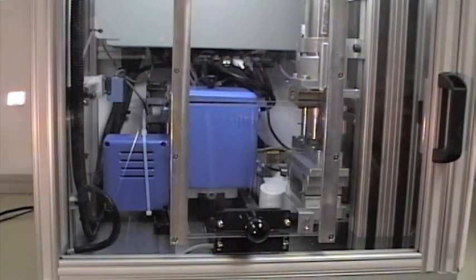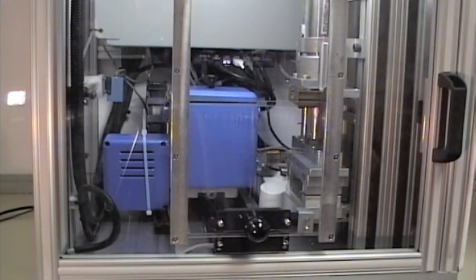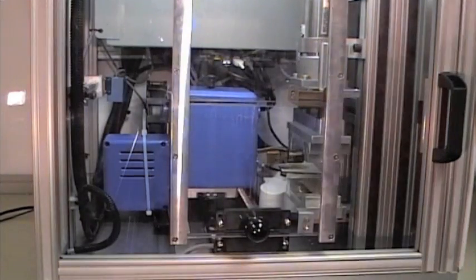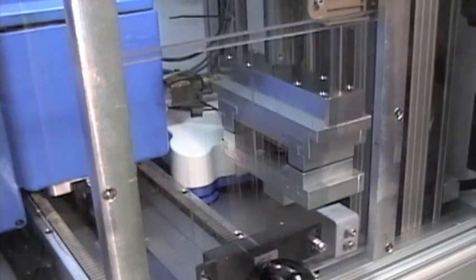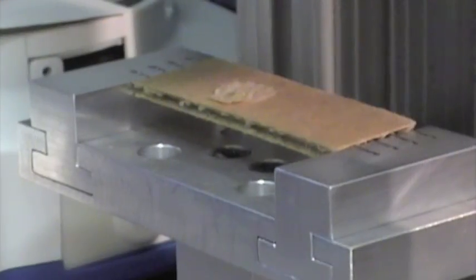Before the test takes place, an actuator sets the pressure over the sample. Once the glue is dispensed and pressure is applied to the cardboard samples, the actuator rises and a load cell registers the maximum amount of force needed to separate the test pieces.